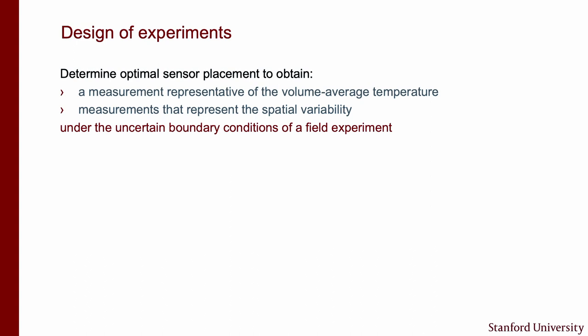So we went to do a design of experiments and then ran our own experiments so we could get data for validation. We wanted to determine optimal sensor placement to get measurements representative of the volume average temperature, as well as measurements that represent the spatial variability—since you might want to know not just the average, but also the minimum and maximum temperatures. And since field experiments mean we can't control the wind and temperature, we need to find sensor locations that work under the whole range of conditions we might see during the experiment.